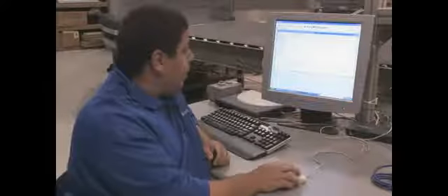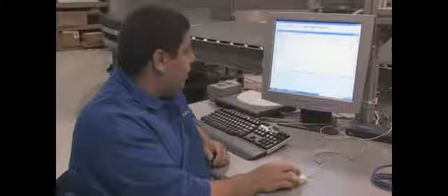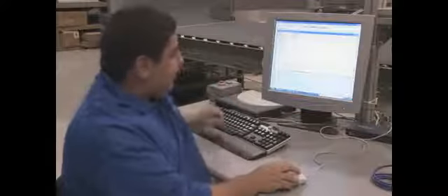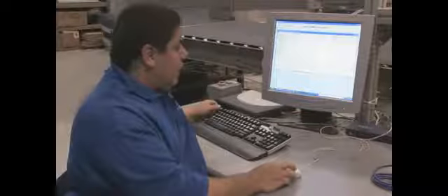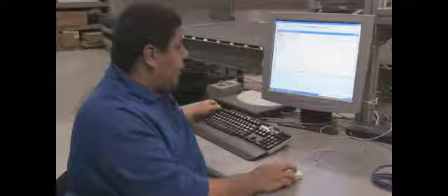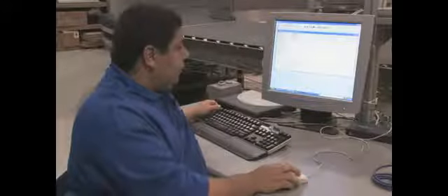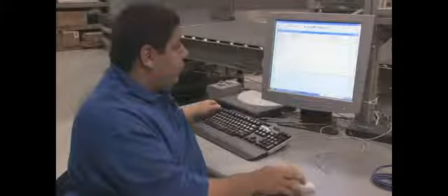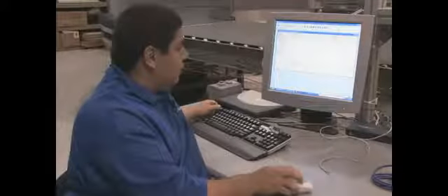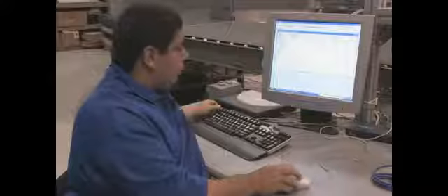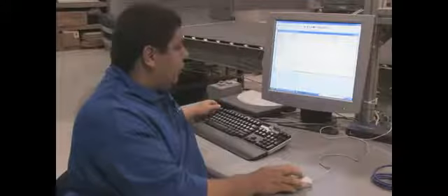It's also possible to toggle the trigger of the scanner by triggering with the PLC. The parameter for that is under Operating Mode. Start Input from Field Bus is the parameter we want to change. Just make sure there's a check mark in that box. With all those settings set, we will go ahead and send this configuration by clicking the Send Configuration icon. You send it to the EEPROM, that way it stores permanently in the scanner.